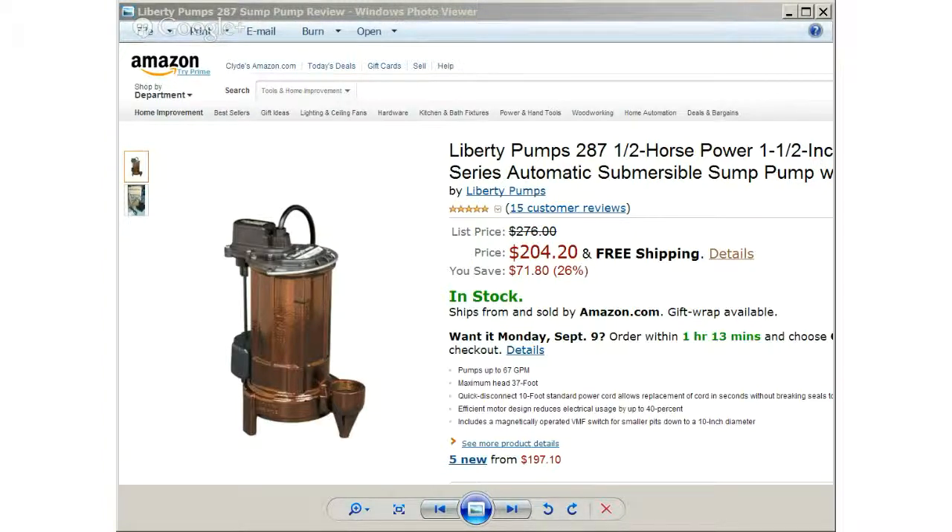The Liberty Pumps 287 1/2 horsepower sump pump includes a magnetically operated VMF switch for smaller sump pump pits down to a 10 inch diameter. It pumps up to 67 gallons per minute with a shutoff head of 37 feet and 3/4 inch solids handling capability.